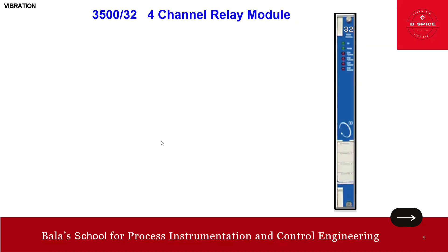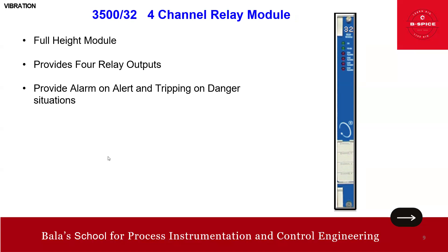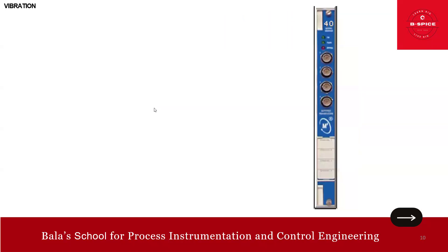Module 32 is the channel relay module. It is a full-height module providing four relay outputs. It provides alarms on alert and tripping on danger situations, and is programmable for AND/OR voting of trip release.